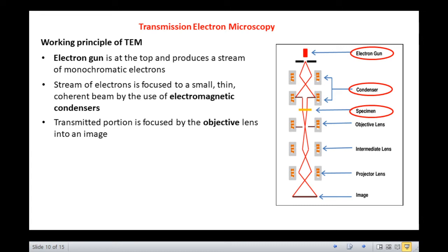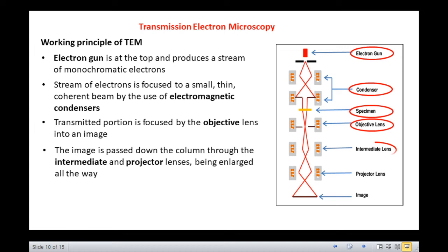This transmitted portion is focused by the objective lens into an image. This image is 2,000 times magnified. The image is then passed down the column through the intermediate and projector lenses, being enlarged all the way. The image strikes the phosphor image screen and light is generated, allowing the user to see the image. The final image is 250,000 times magnified.